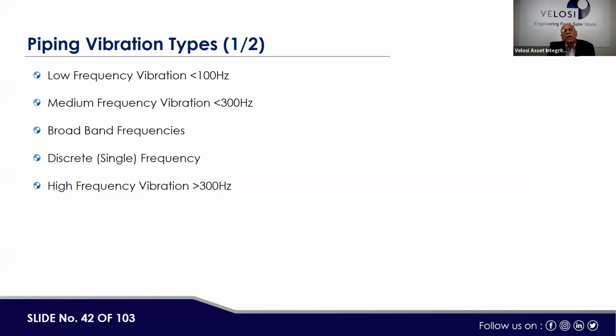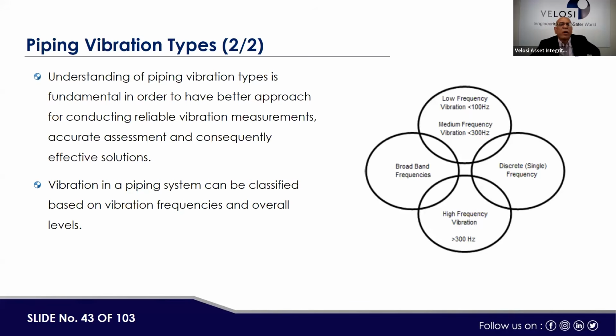So next part, piping vibration types. Low frequency vibration is one type, then medium frequency vibration, and broadband frequencies. So less than 100 hertz, then over 300 hertz, then discrete single frequency, and high frequency vibrations are also there. These terminologies we need to keep in mind when we go to the next stage. Understanding the piping vibration types is fundamental to having a better approach for conducting reliable vibration measurements, accurate assessments, and consequently effective solutions.